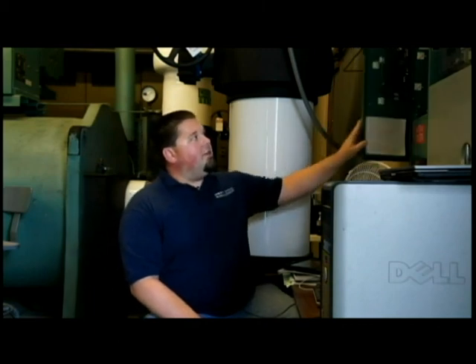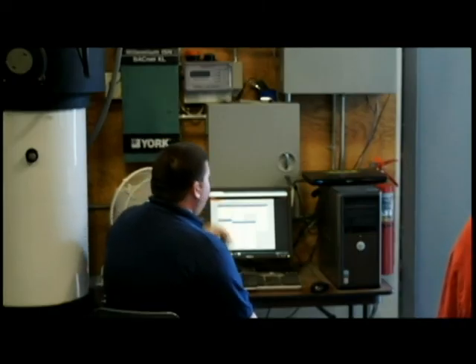When that happens, the lead chiller actually gets enabled through BACnet. There is no hardwire command to these systems. What we do is speak through a BACnet interface up here in this York panel, and we pass the command over the network to tell whichever chiller we would like to run or begin to run. In order to get the chiller running, we also have to have the condenser water pumps running. So they start up at the same time as the chilled water side, so that we make sure we have flow through both sides of the chiller before we ever try to run that chiller.